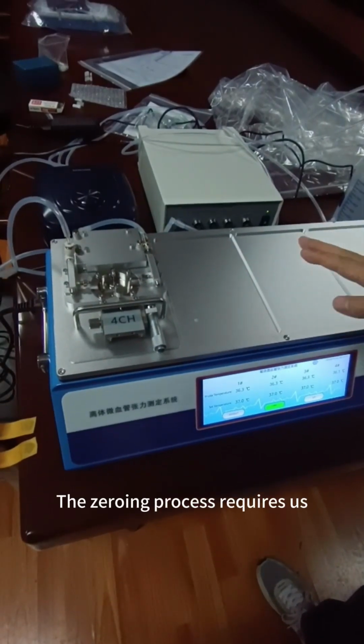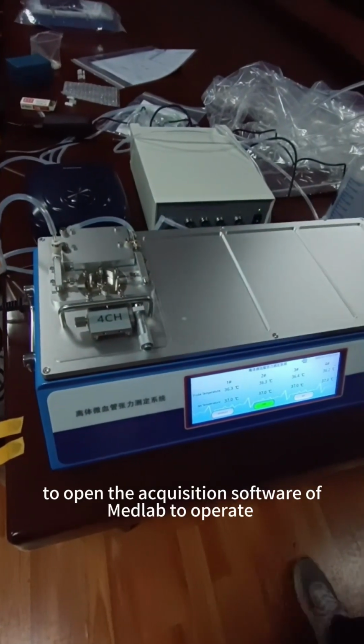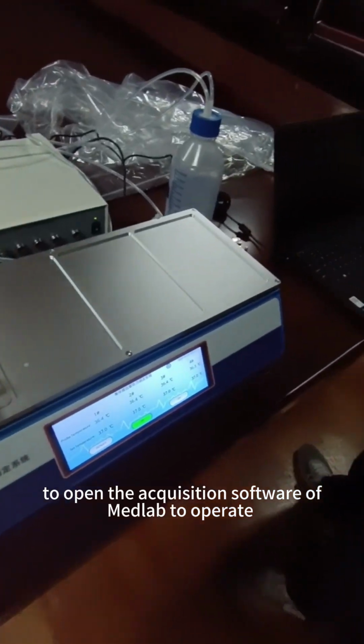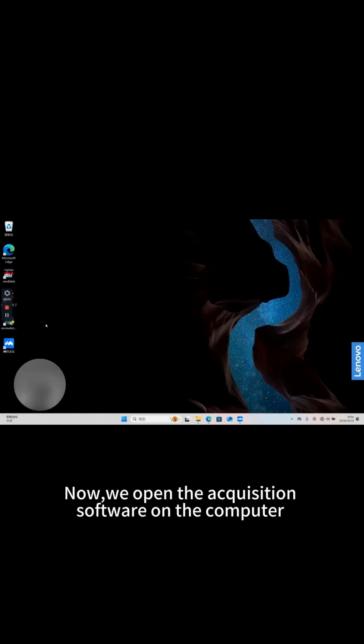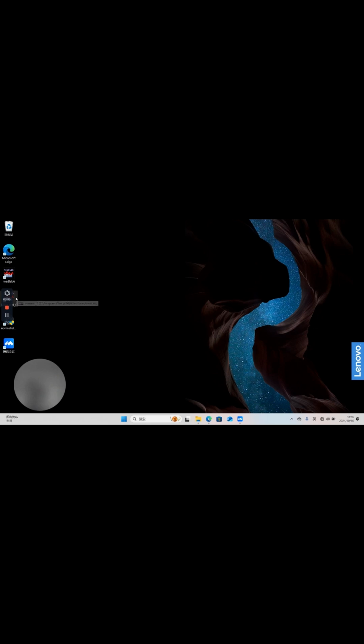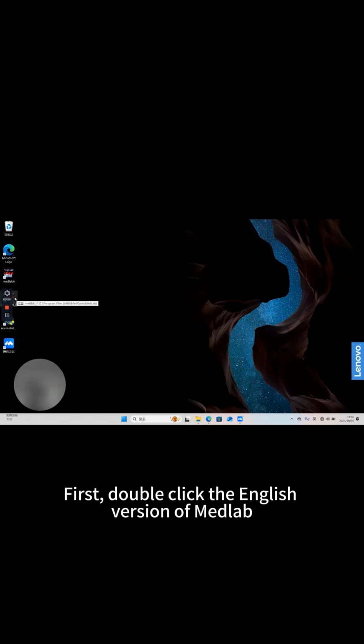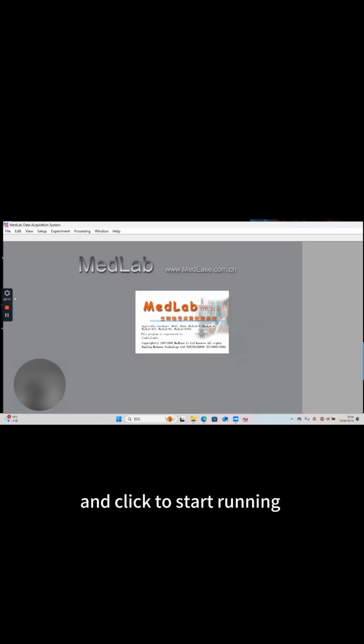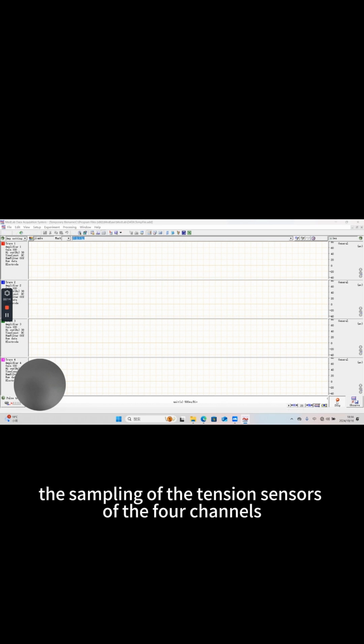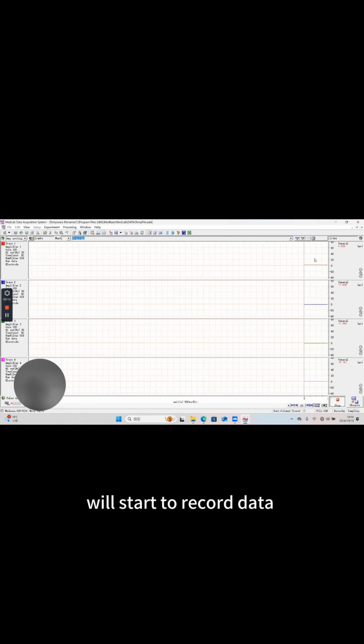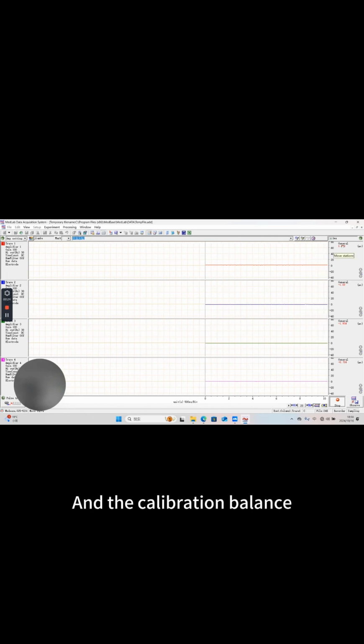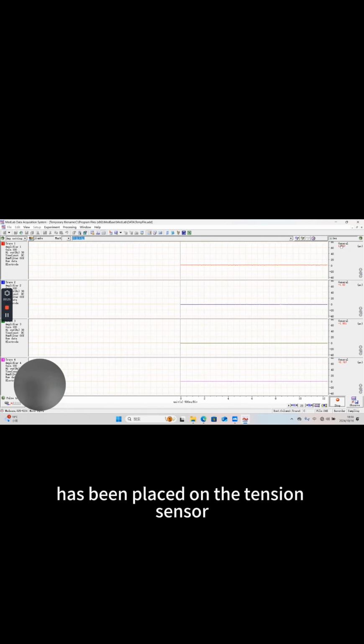The zeroing process requires us to open the acquisition software of MedLab to operate. Now we open the acquisition software on the computer. First, double-click the English version of MedLab and click to start running. At the beginning, the sampling of the tension sensors of the 4 channels will start to record data. Here, the first channel is used for tension demonstration, and the calibration balance has been placed on the tension sensor.